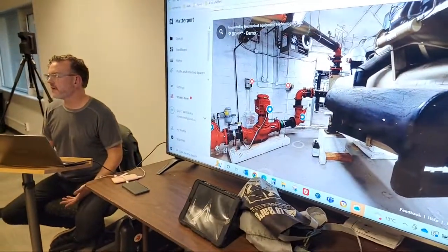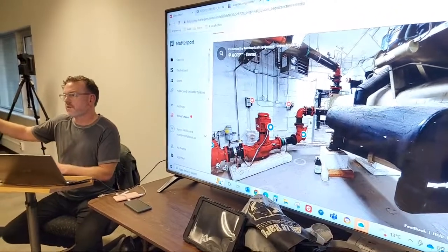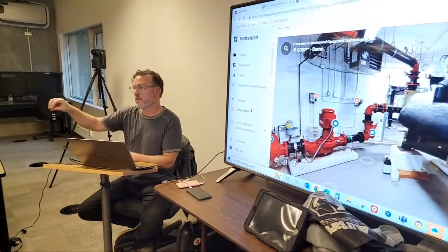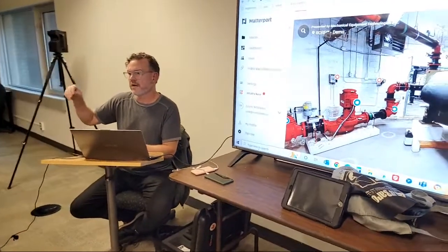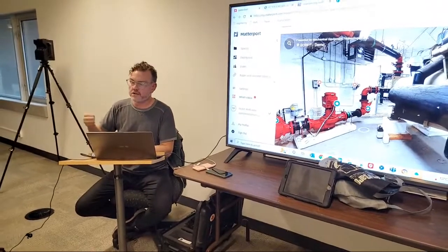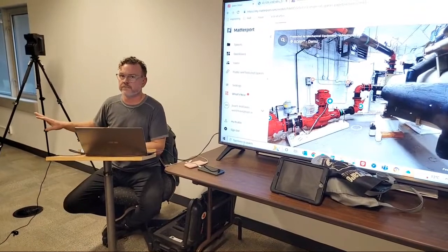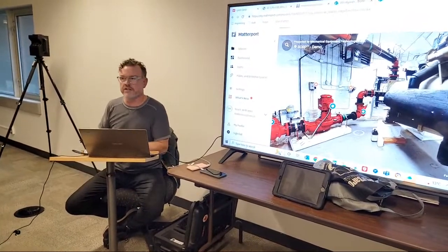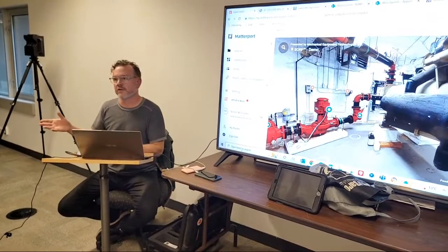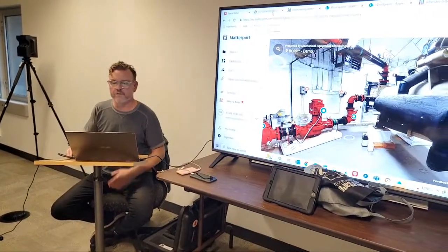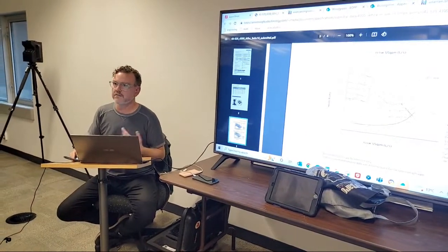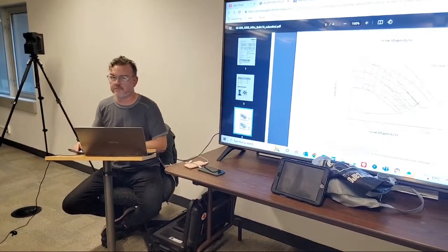And everything in an HVAC system, in a building system, in a mechanical room, has a cascade effect. So you might have something that's starting over on this side here. It could be the pump, it could be the tower, it could be a heat exchanger, and there's an additive effect that happens, and all of a sudden something's not operating right in another area of the system. Well, the knee-jerk reaction is that's what the issue is. No, we have to look at the flow, the pressure, the delta pressure, and the delta T's, and understand how design flow impacts, and how pressure impacts pumps and all that, right?